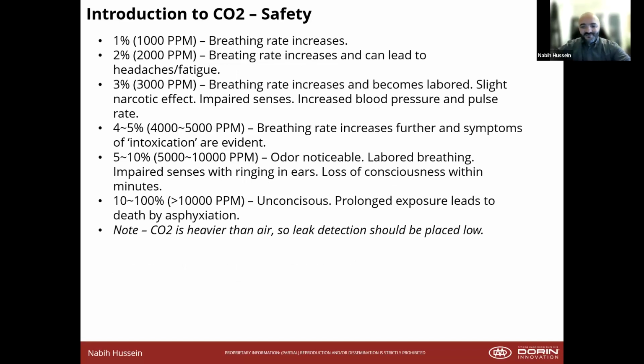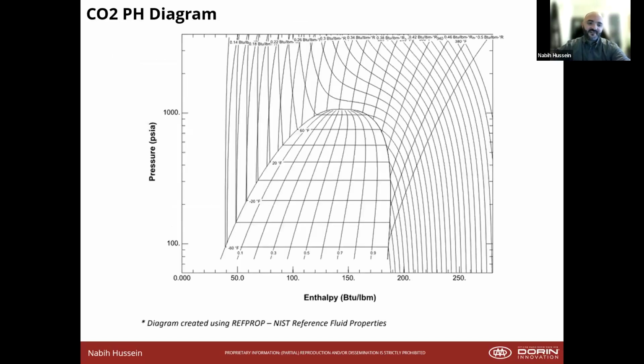CO2 safety, mostly a safe refrigerant. At 1%, you have breathing rate increase up until 4 to 5%. You're looking at an intoxicant effect. At 5 to 10%, you should be able to notice the smell, but it's described as a very sterile smell. Loss of consciousness may happen within minutes, and then 10 to 100% is unconscious after prolonged time and possible asphyxiation. So, for the most part, very, very safe, but it is good to be cognizant of the dangers.